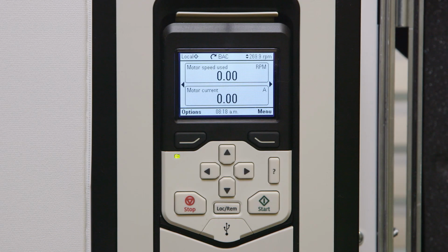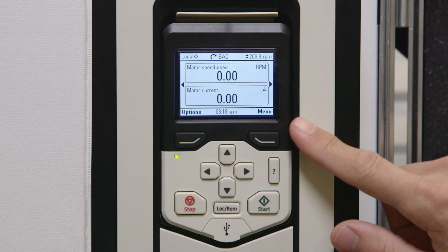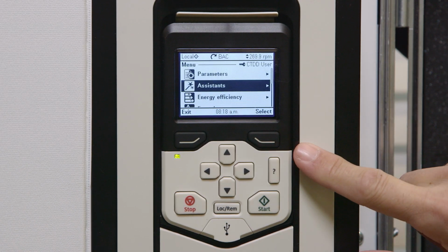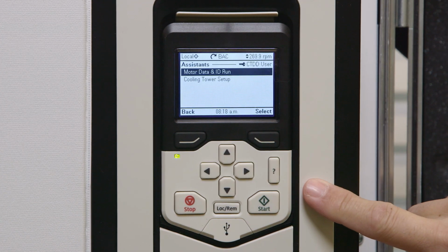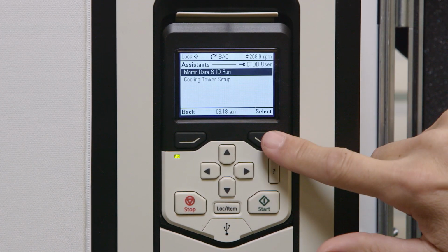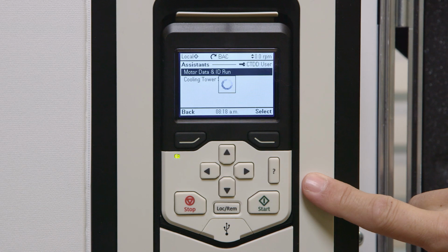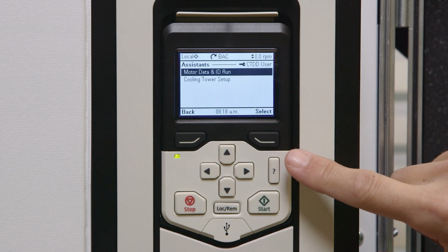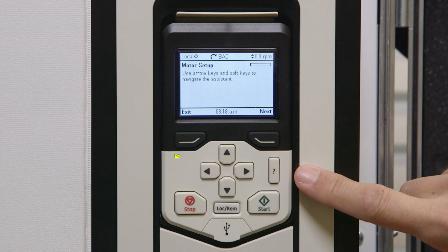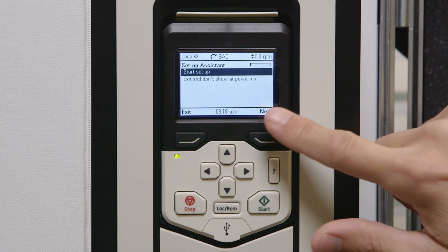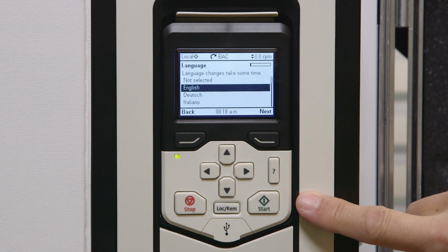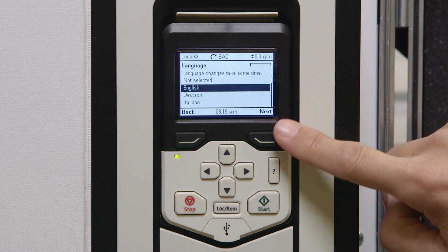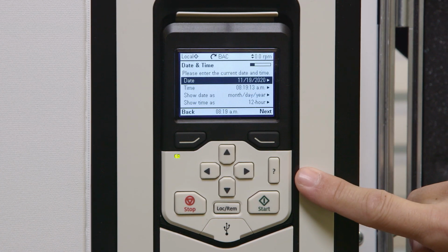On initial startup, the VFD asks for a language selection. If you do not see this, navigate to it by pressing Menu, then Assistants, press Select at Motor Data and ID Run. At Motor Setup, press Next. Then press Next again at Start Setup. With the language option now on display, choose the appropriate language. Here we've selected English. Press Next.